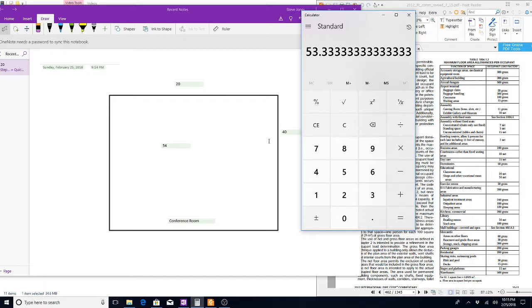The other thing we know is that because it has two exits, any time that happens, the doors have to swing in the direction of egress. If we only had 39 people, that door could swing into the room. But because it's more than 49, the door has to swing out — so both doors will have to swing out.